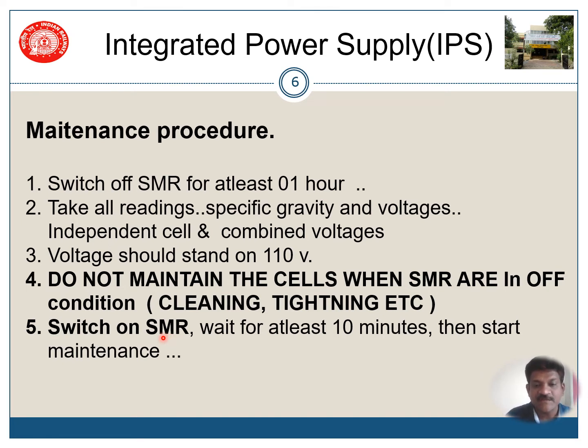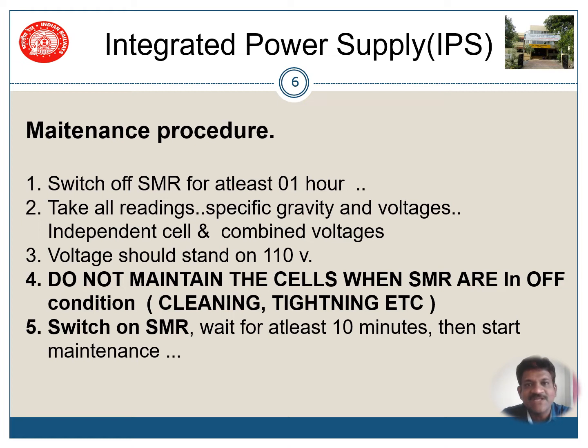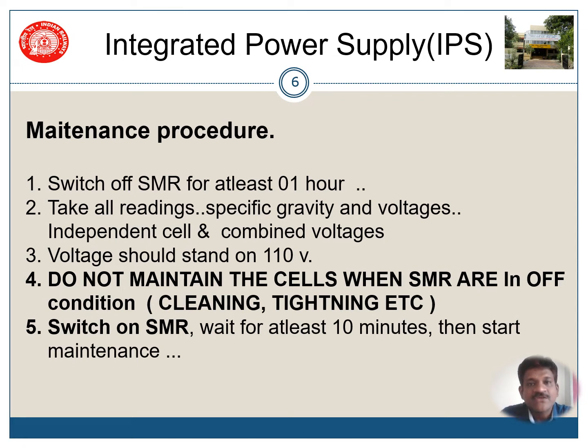Switch on your SMRs and wait for at least 10 minutes. Ten minutes is required to settle the battery, because excess current being taken by the battery could cause the switch to go defective. To rule out any such problems, wait for 10 minutes and then do the maintenance of the cells.